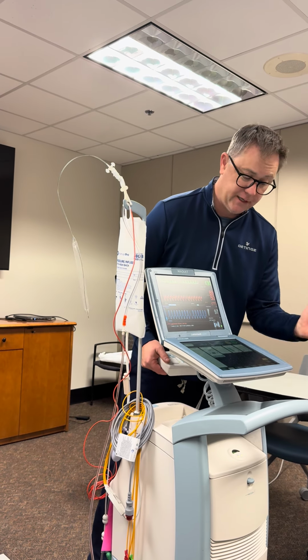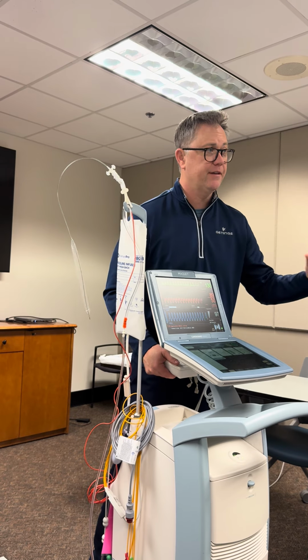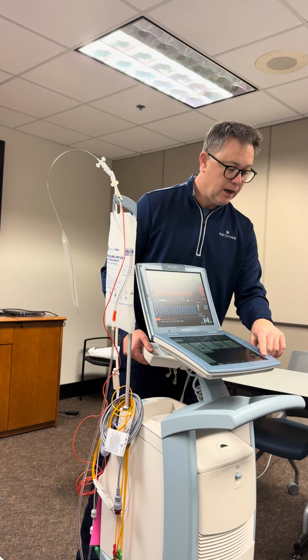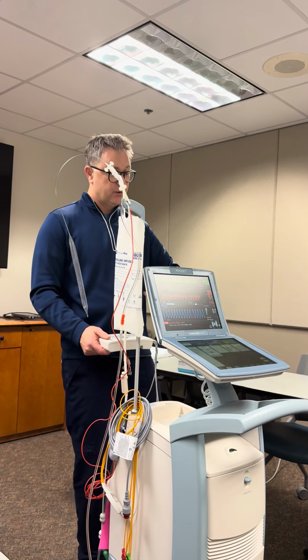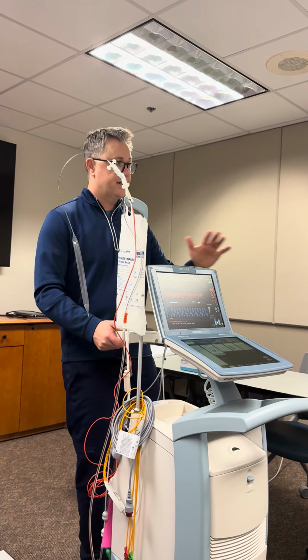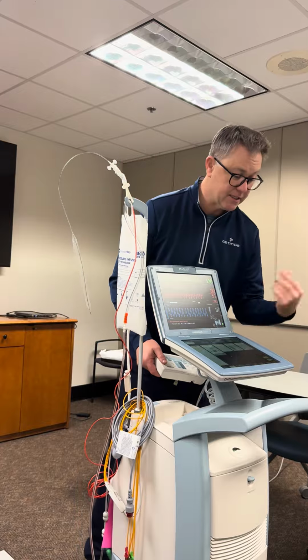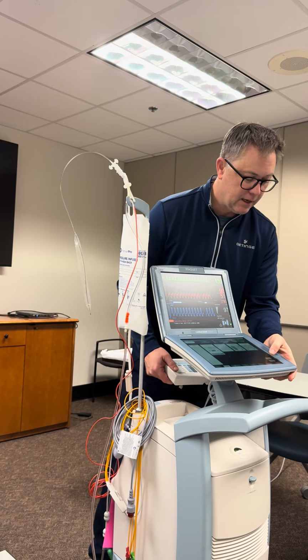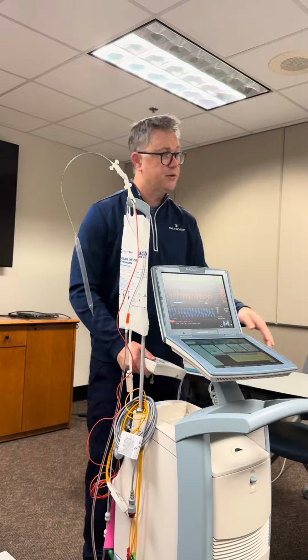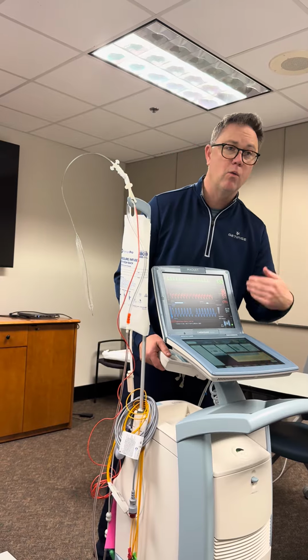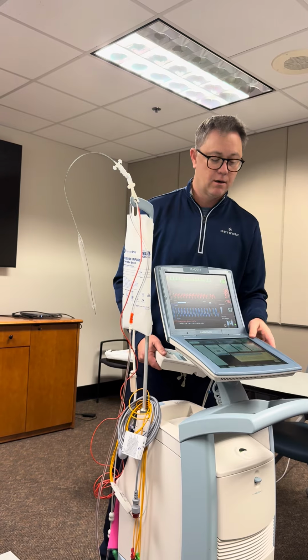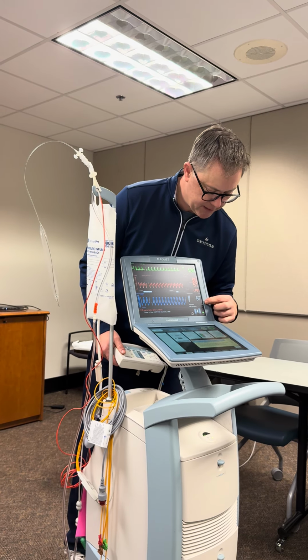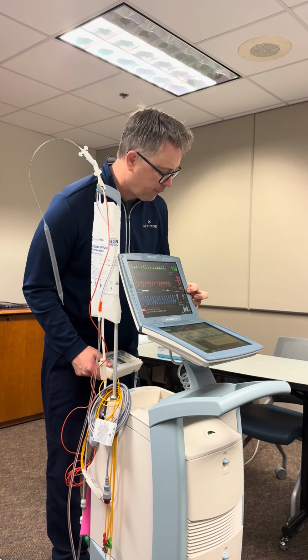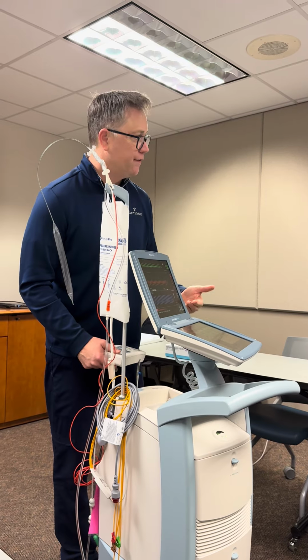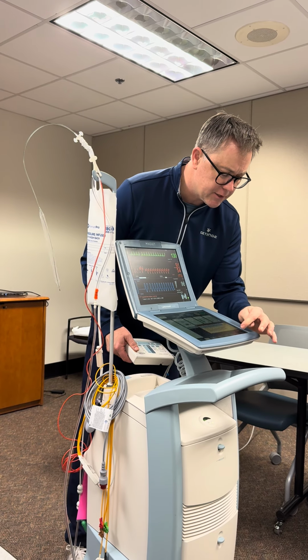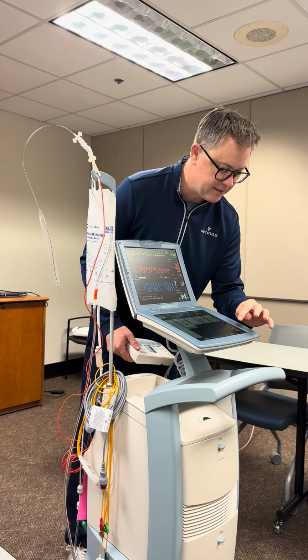Whenever you get an alarm, the first thing I recommend doing is going to pause audio to get rid of that annoying alarm. It's terrible. Pause audio is going to get rid of the alarm for 60 seconds unless you fix it. So every 60 seconds, it's going to go off until you fix it. The other thing I recommend is the help screen. I wish it would just automatically pop up, but if you go to the help screen, it will walk you through whatever the issue is with the alarm. In this case, it's going to tell me that my augmentation alarm is set too high. It's at 104, and we're currently augmenting at 97. We've fallen below, we've tripped it, right? So I didn't fix it in time.